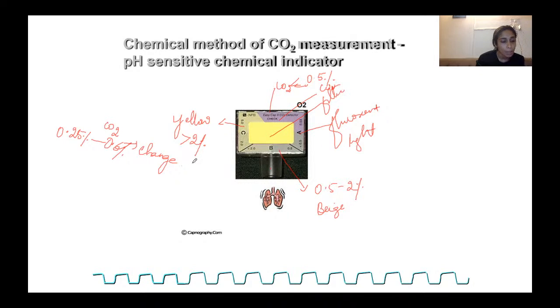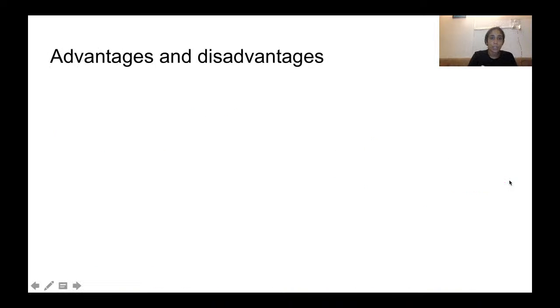The hygroscopic carbon dioxide detector can last for a few minutes to several hours, depending upon the humidity of the gas. If an HME filter is used, it reduces the humidity of gases and can prolong the carbon dioxide measurement. So an HME will increase the measurement time. It depends on the humidity.